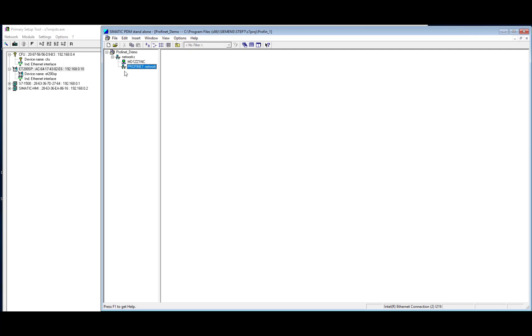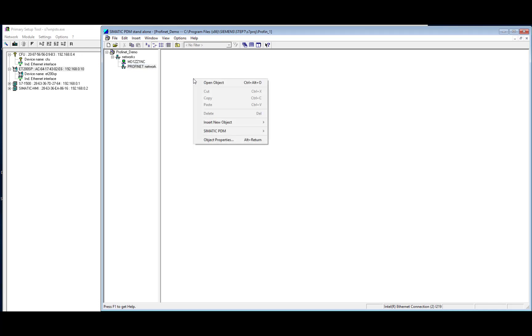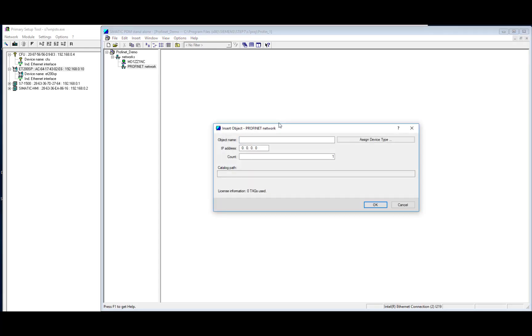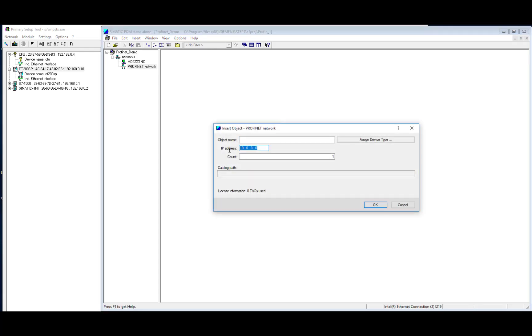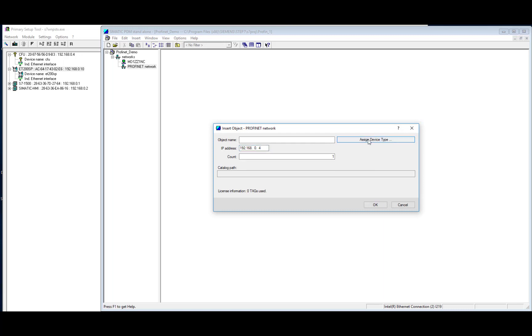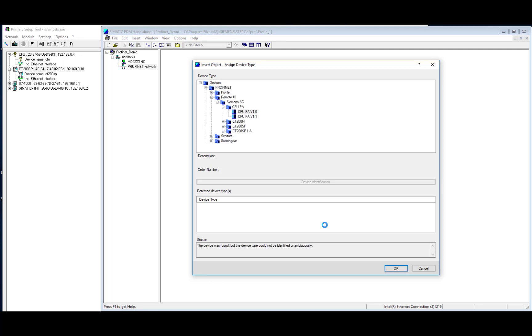So the next thing I need to do is to add a new device. And we will start with the Compact Field Unit, so right-click, insert new object. And we'll put in the IP address that we've already discovered by using the Primary Setup tool. So in this case, 192.168.0.4. And if we click on Assign Device Type, and then select Device Identification, PDM will tell us what the connected device is.